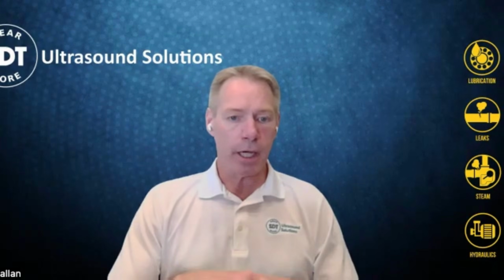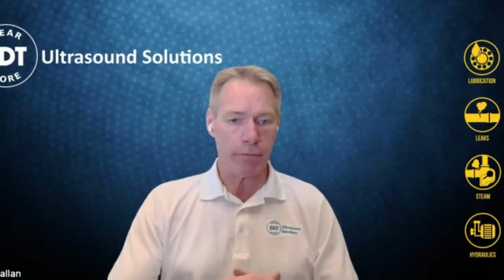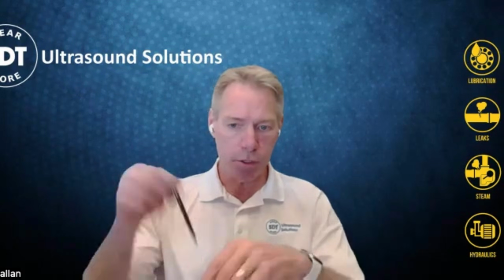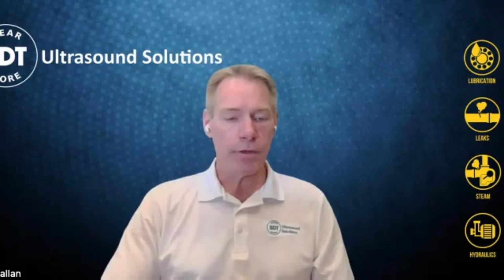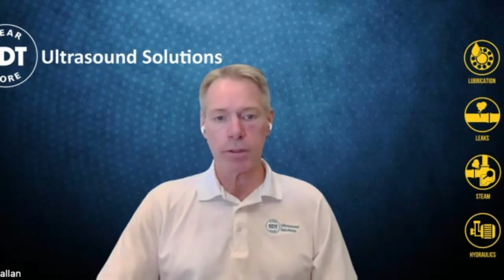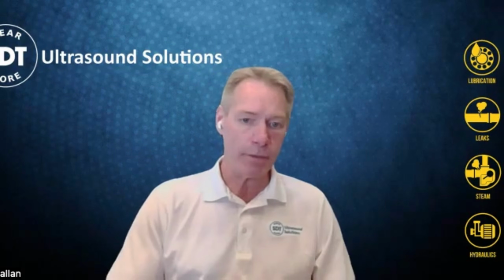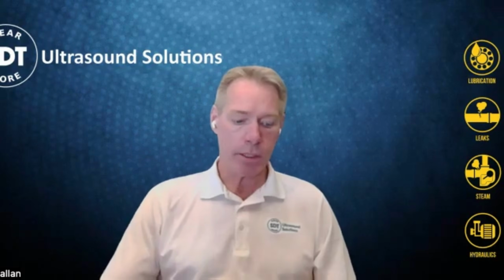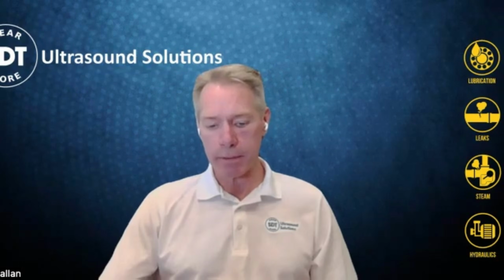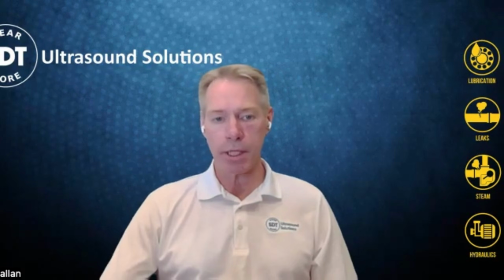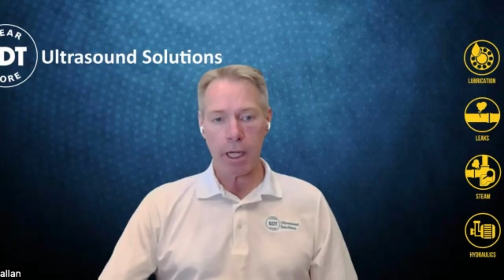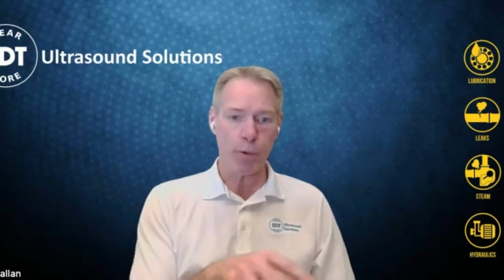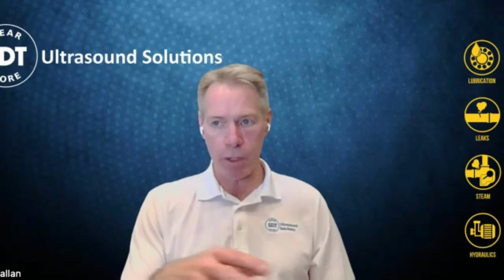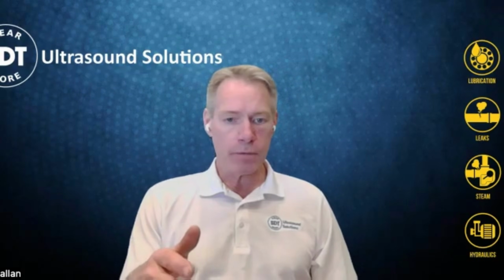Valves, again, if you've got any kind of a flow across a valve, you're going to have turbulence. And so we can just put a contact probe on the valve, and we can hear whether or not the valve is blocked, if it's cavitating, if it's passing, all of those types of things. And that translates into hydraulics, which is another application pillar, hydraulic systems. So you've got flow through pipes, you've got flow through valves and diverters.